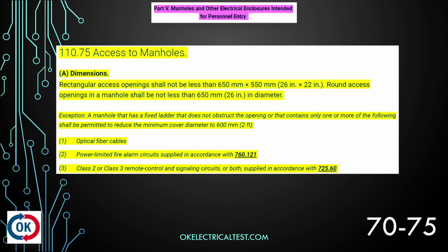And letter A, dimensions. Rectangular access openings shall not be less than 26 inches by 22. Round access openings in a manhole shall not be less than 26 inches in diameter. Now, look down below here, we've got an exception to that. So minimum round is going to be 26 inches, except a manhole that has a fixed ladder that does not obstruct the opening, or that contains only one or more of the following, shall be permitted to reduce the minimum cover diameter to 2 feet. So if I've got a fixed ladder, or if I've got any of these cables or any mixture of these cables down in the manhole, then we can reduce that down from 26 inches to 2 feet.